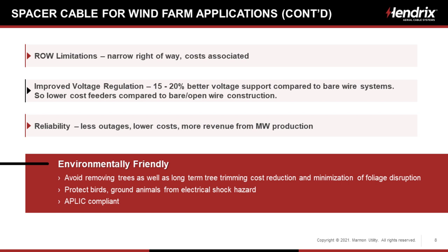We're also using it when we have right-of-way limitations, when we have a narrow right-of-way, or it's a narrow right-of-way because they won't allow us to remove the trees. We know we're going to get improved voltage regulation. We're going to have 15 to 20% better voltage support compared to bare wire systems, and this is going to lead to lower cost feeders because we're going to end up buying less aluminum. We're going to have vastly improved reliability, less outages, lower costs, and more revenue from megawatt production.